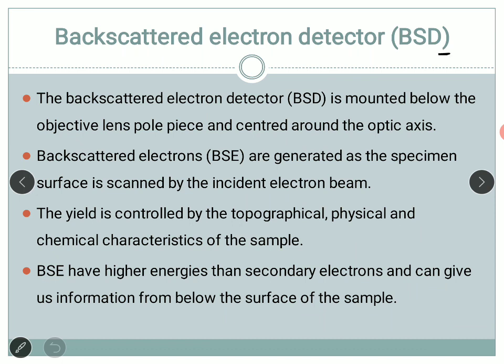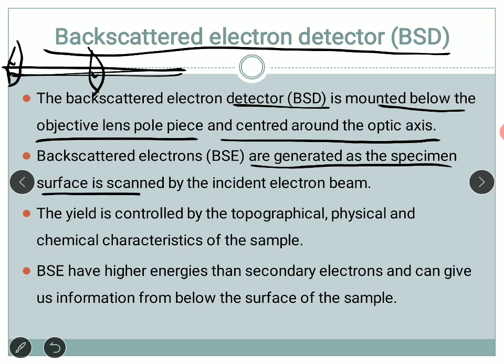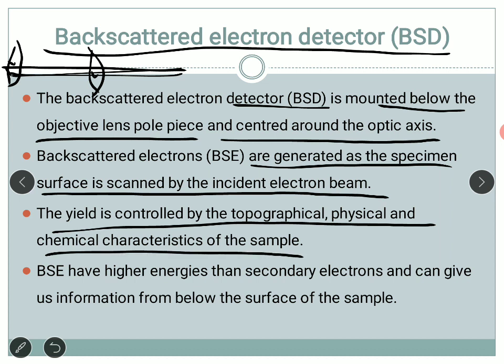For the backscattered electron detector, the positioning is different. These detectors are mounted below the objective lens pole piece and centered around the optic axis, just above the sample. They are generated as the specimen surface is scanned by the incident electron beam, along with secondary electrons. The yield of backscattered electrons is controlled by the topography and the physical and chemical characteristics of the sample. This means backscattered electrons can provide information about topography as well as physical and chemical properties. Backscattered electrons have higher energy than secondary electrons but lower resolution, giving information from below the surface.